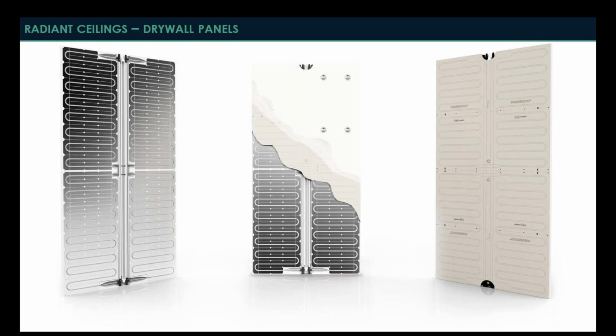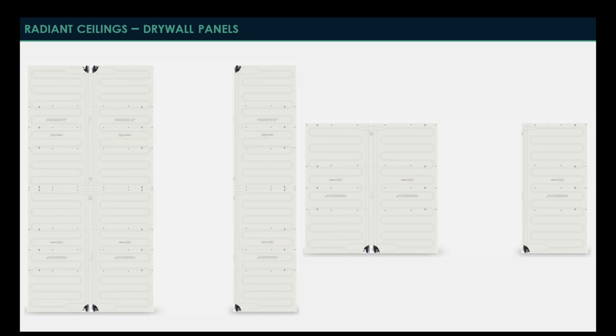So essentially all you have to do with this type of system is bring it out into the field and install it into your ceiling adjacent to a normal drywall ceiling panel, and then you mud the joints, you tape it, you sand it down, and then you paint it as if it was any other surface. And essentially what you end up with is a completely seamless drywall ceiling with portions of it activated as radiant cooling and heating. It's also a unique product in that it comes in a 4x8 sheet and can essentially be field cut into different dimensions, whether that's split in half vertically or horizontally to give you a 2x8 or a 4x4 type application, or it can be quartered into a more traditional 2x4 panel size. So it offers a lot of flexibility in terms of how you order the product, how it can be installed, and how it's treated in the field.